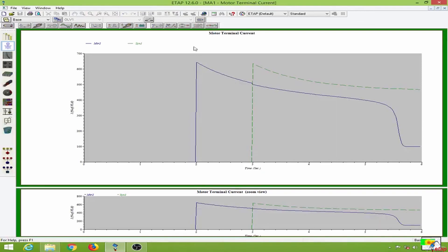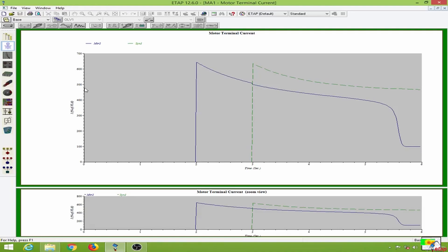So the motor terminal current reaches to a peak of more than 600 amps. This is about 600% of the full load current over here, and this reduces over here. Similar is the case of the synchronous motor as well.